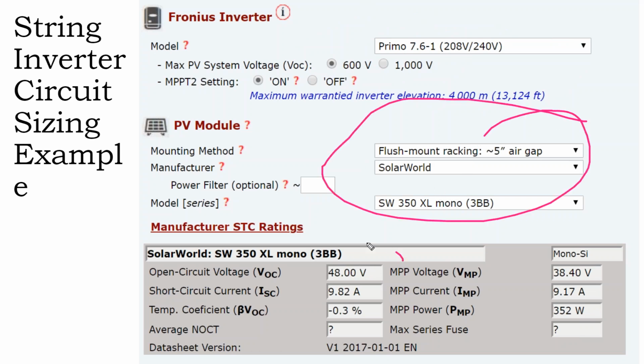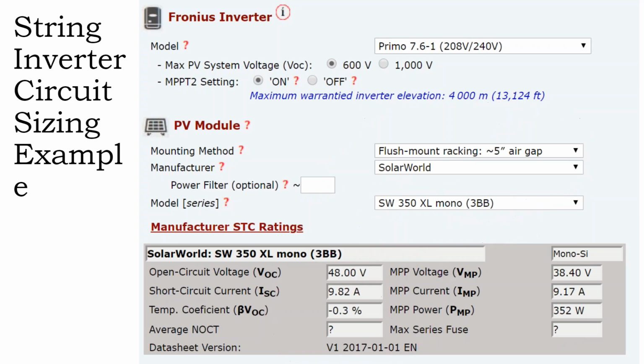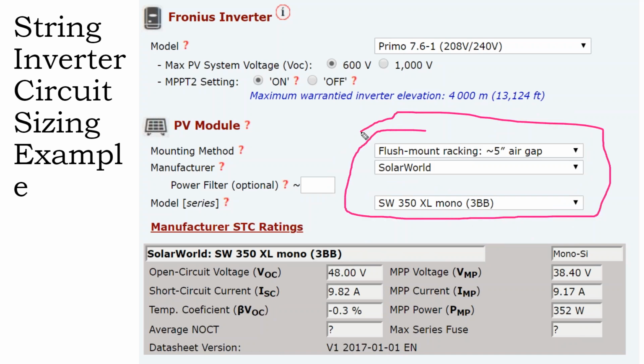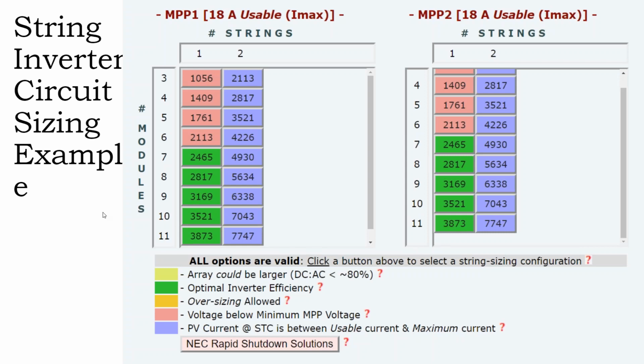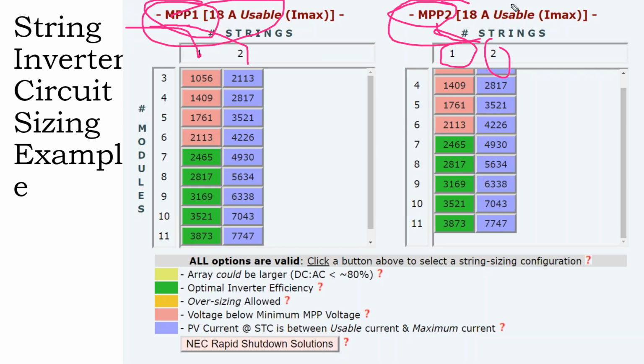You're putting in your modules, and it's giving you the voltages and the amperages that are pulled off your specific solar panel's spec sheet. So these manufacturer string sizing softwares just have a database of like every solar panel out there, young and old. And then we get to a screen that will tell us, okay, my string inverter can have 2 circuits on input 1 and 2 other circuits on input 2. These are called maximum power point tracking for the inverter itself. I think that's a distracting term. I would just call it, MPP1 is input 1 and MPP2 is input 2.